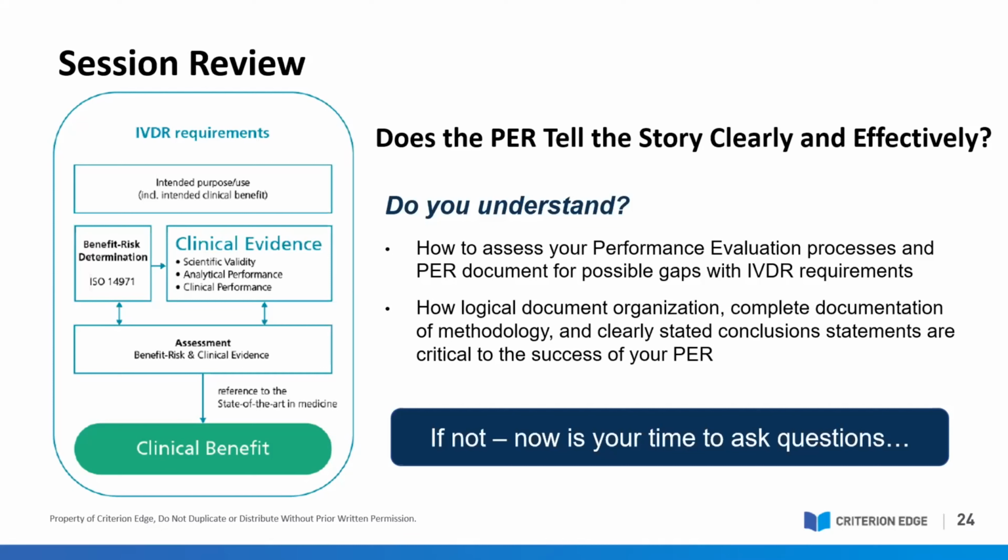So as you're evaluating your own PER, ask yourself these questions. Is there sufficient information within this report? Can the report be read and understood by an independent third party that does not know your company's device as well as you do? Those are really the two guiding benchmark principles to assess the state of your PER against. Is there data sufficiency, and is the data presented understandable and easily presented in a very clear and organized way?